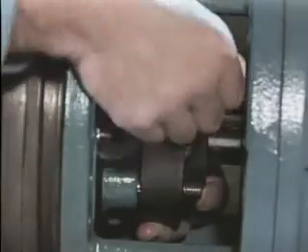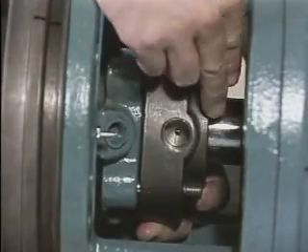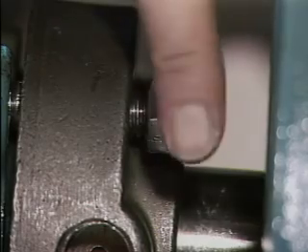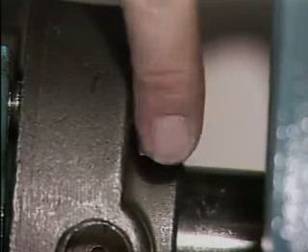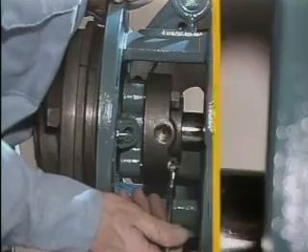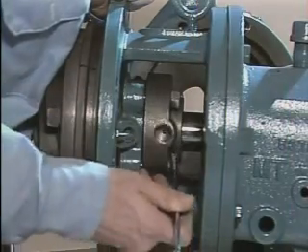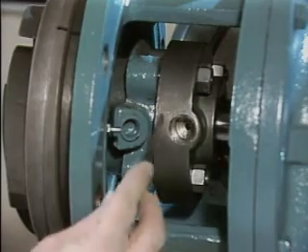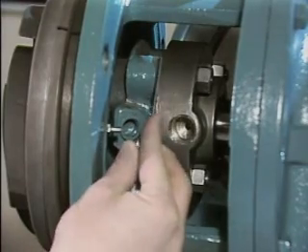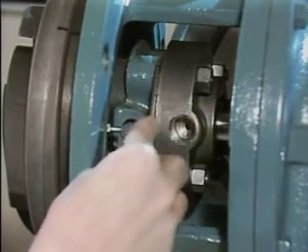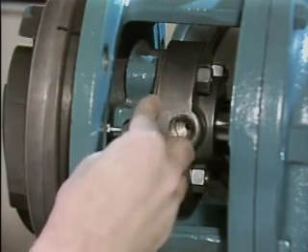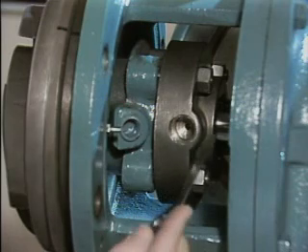The plate is slid along the shaft toward the stuffing box. The gland plate nuts are then installed and tightened until the gland plate is snug against the stuffing box. Over-tightening these nuts could warp and damage the mating ring. To ensure that the nuts have been tightened uniformly, the gap between the gland plate and the stuffing box is measured at each gland plate bolt. If the gland plate is properly installed, the measurements should all be the same.